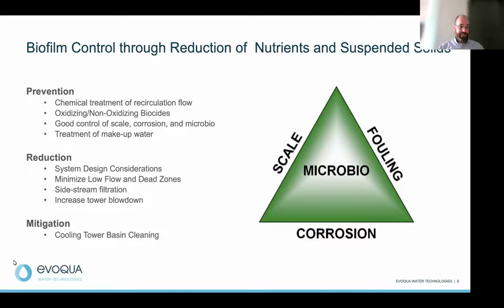Secondly, there's reduction. Maybe there's some great engineering work that's been done to engineer the systems to remove or reduce low flow zones and dead legs and those sorts of things. Maybe that does include some side stream filtration. And then lastly, there's mitigation. Maybe you have your annual or semi-annual cooling tower cleaning and disinfections. Maybe you're doing it due to remediation. You've had perhaps a problem or high Legionella levels, but that's what's typically been done to help you reduce the amount of chiller maintenance that you have to do. So prevention, reduction, and mitigation.